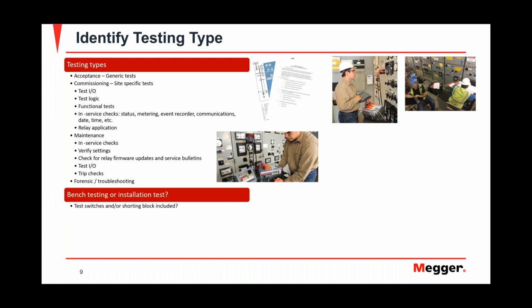Another thing to know when you're going, hey, am I just bench testing this thing? In that case, the customer could ship you the relay and you're just doing it on your desk. If you're doing an acceptance test just with bench testing, or is it a relay that's installed in a piece of switchgear? In that case, you have to bring more equipment. You have to bring probably test paddles. We're going to go into defining the area of protection. So when you go out there, that lets you know what type of tools and what type of things you should bring with you when you do the testing.